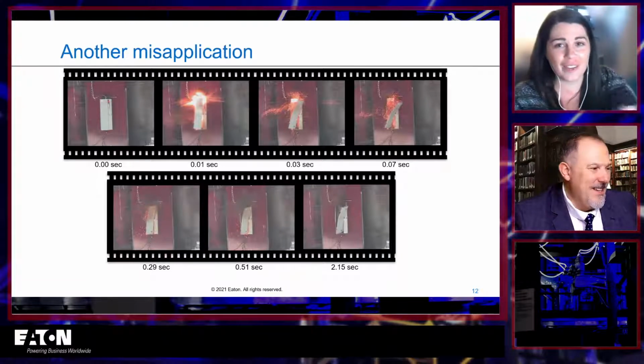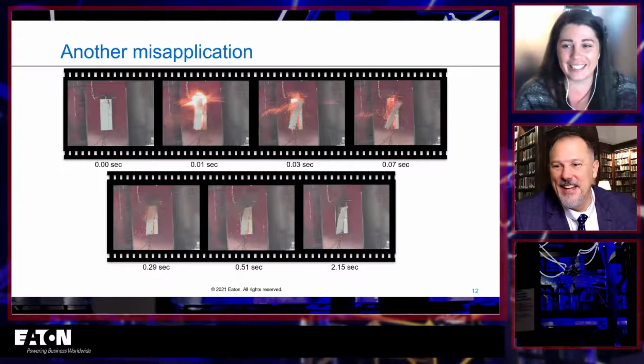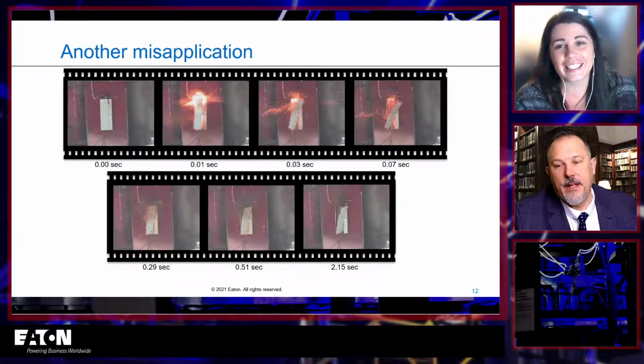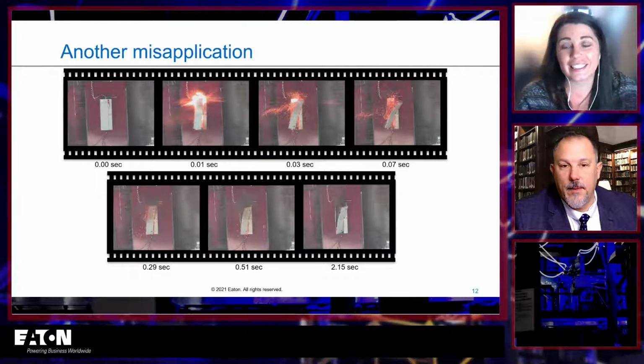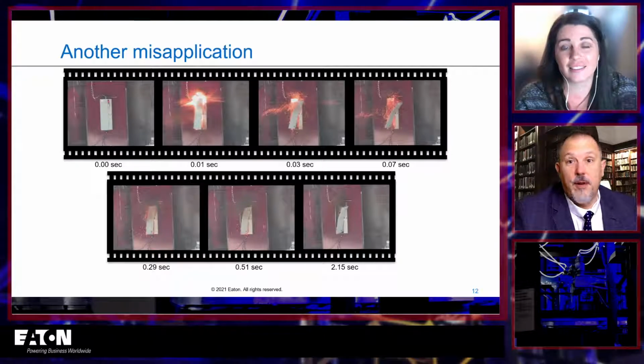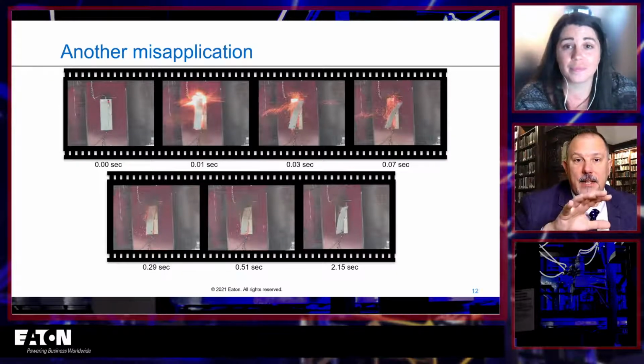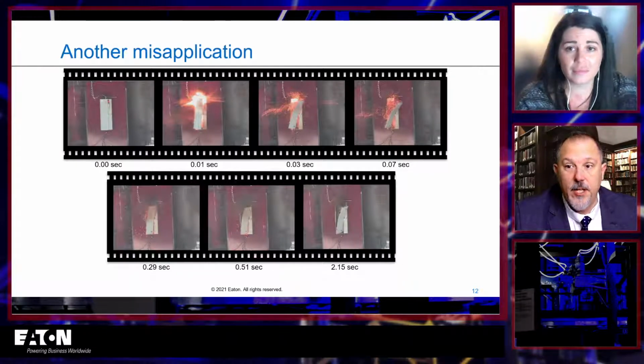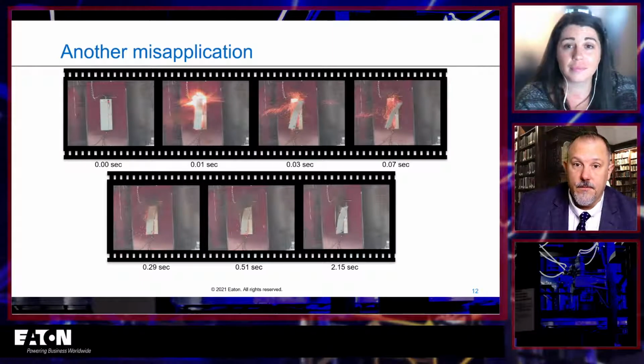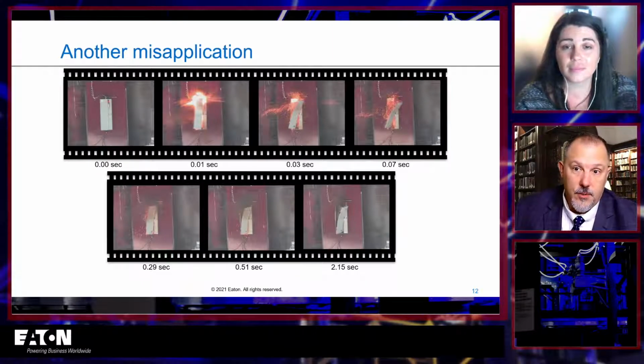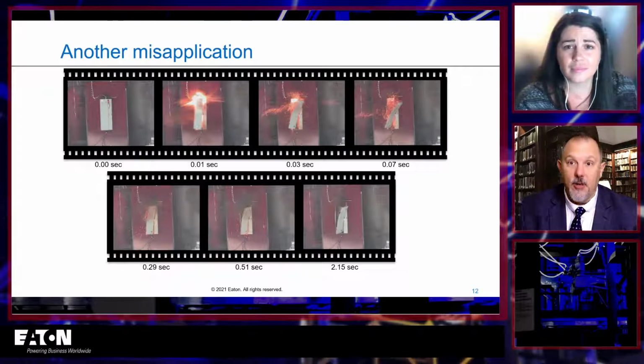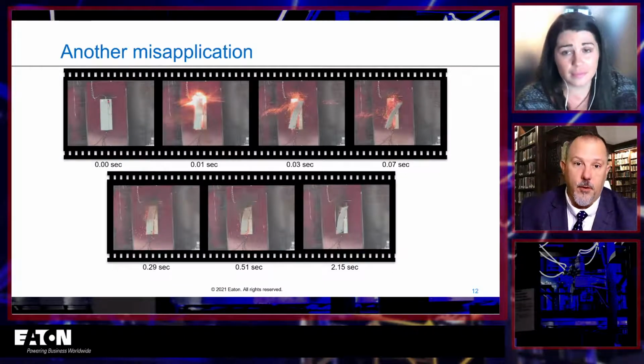If you can find a way to reset a fuse, let me know. Yeah. And I would say that if you're below the interrupting rating of the fuse, you're up around 200,000 amps, right? And to our earlier discussion, 110.10 says that you can still have damage to the equipment. If you have a fault that's close to the interrupting rating of a fuse, you're going to be looking at that equipment overall and doing some further analysis before you put it back into service.